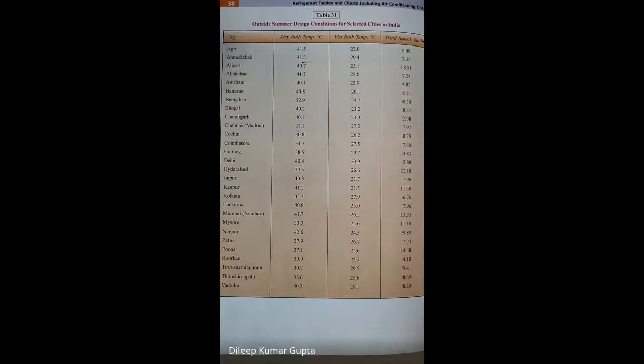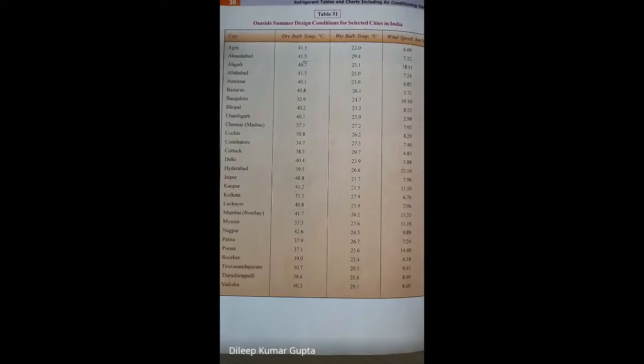Secondly, we had designed for 41.5 degrees centigrade dry bulb and 29.4 degrees centigrade wet bulb temperature. There's a possibility that when temperature reaches 45 degrees centigrade, the wet bulb temperature goes down. Not only dry bulb temperature, wet bulb temperature also plays an important role in heat load calculation. Therefore, the net heat load required for this condition remains almost the same, which gets compensated - two factors help compensate the load when temperature rises.